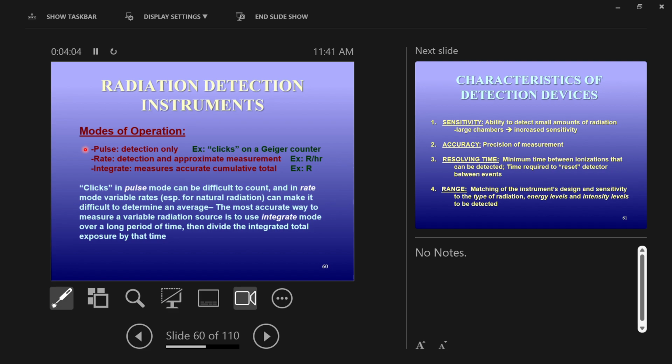What are we measuring? What are we looking for? Exposure. Right, which is what? Intensity. Intensity of radiation above the surface of the object, right? And so what are you measuring? Is your detector measuring an amount of radiation? Or is it measuring something else and inferring the amount of radiation? Of the air, right, in the room, right? It's measuring ionization events, which generates an amount of electric current. The little computers read the electric current and infer amounts of radiation from that, right?